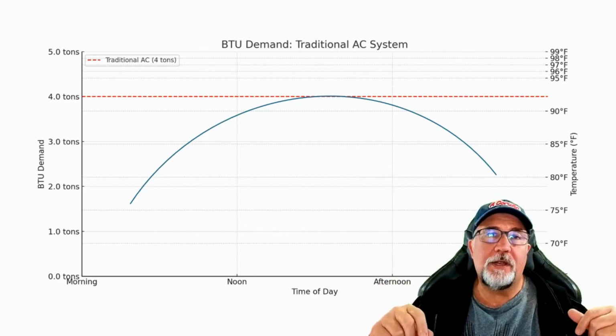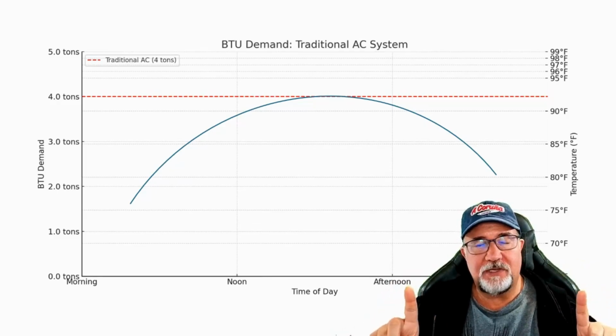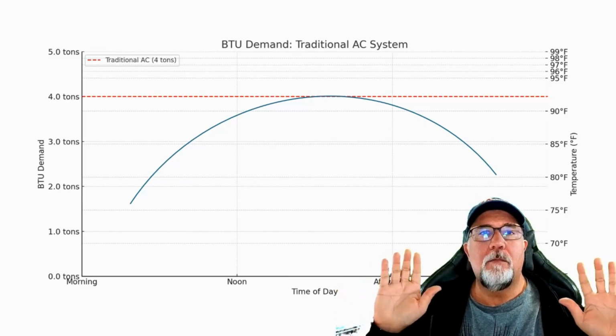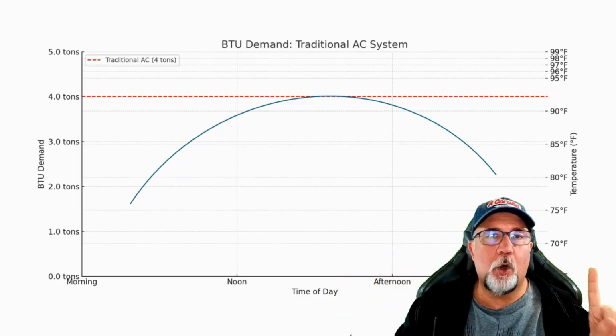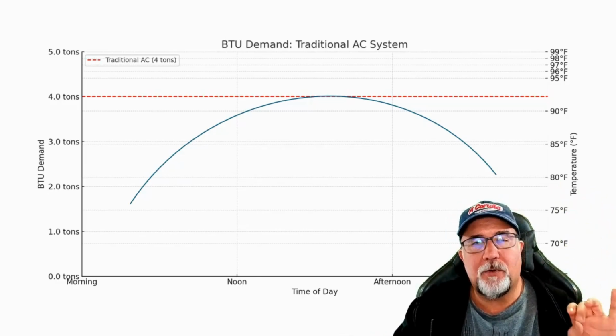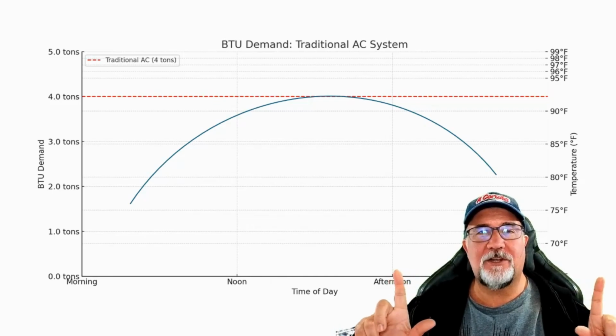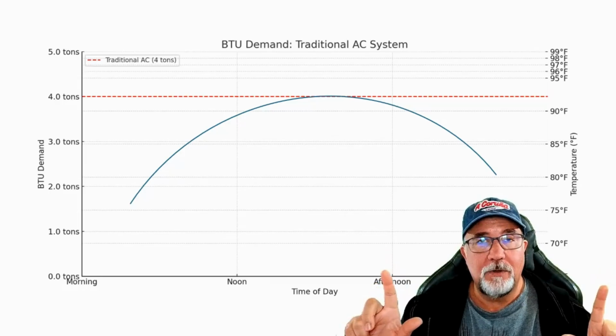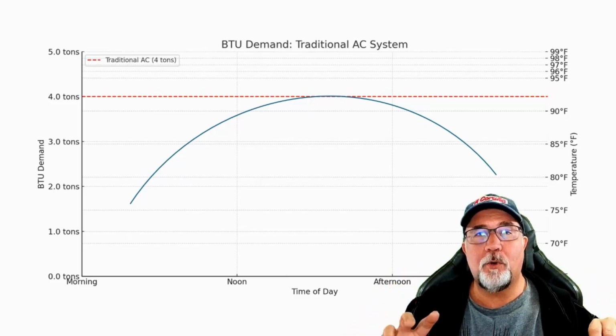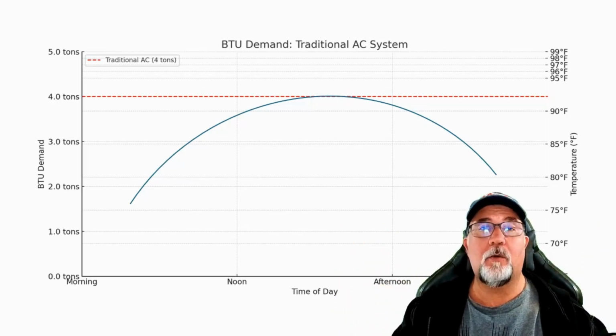When you're properly zoning, a standard air conditioning system, and I know I'm going to get flak from this, and we can go back and forth all day long for you tech savvy people out there, is an air conditioning system that comes on, goes up to 1 tonnage and shuts off, is not the proper system for zoning. Okay. All right. Here's where these guys are going to kick in and go, he's full of it. No. Yes, you can take a system that's one size and one size only, and you can put what's called a bypass damper. And I don't want to get technical. When I do the book, I'm going to get real technical about bypass dampers.